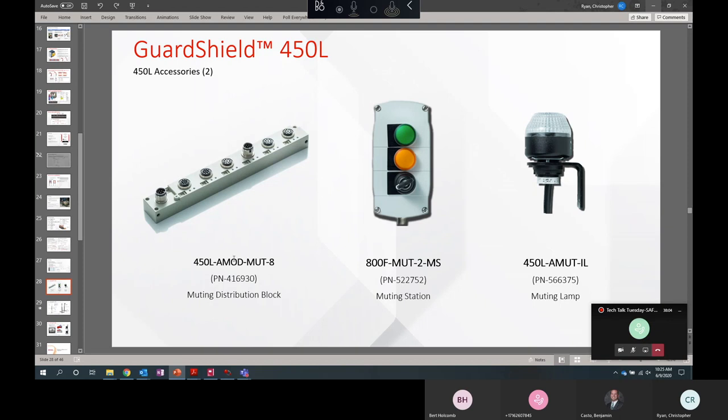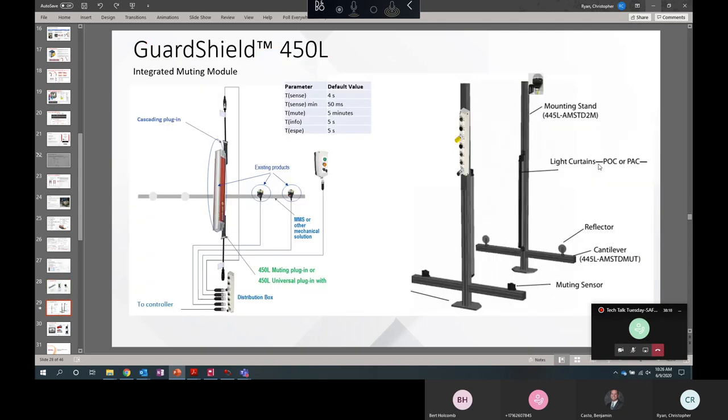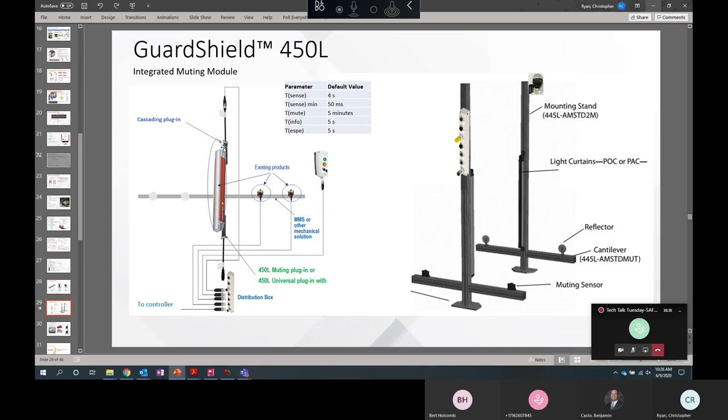And these are some accessories for muting. These are new accessories. We have a muting block to make it very simple to plug in your muting sensors and your light curtain. We have a muting station here for your mute-dependent override light and your selector. And then we have a muting lamp. We also have a muting stand. This can be bought with or without these cantilever arms that hold your muting sensors. We have a few different types of stands you can use. But this makes it very simple to set up an advanced muting application with a light curtain. Four-sensor muting requires a cascading plug-in to wire those additional sensors. If you're using one of the two-sensor muting application types, those sensors can be wired to the muting block or directly to the muting plug-in.